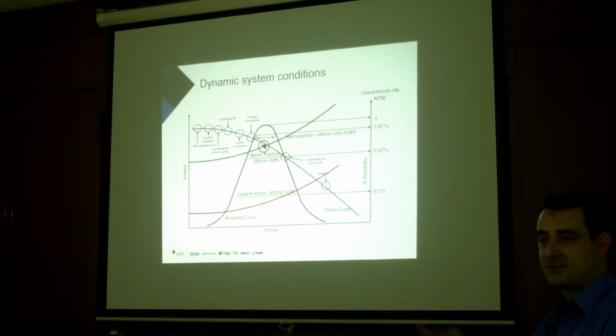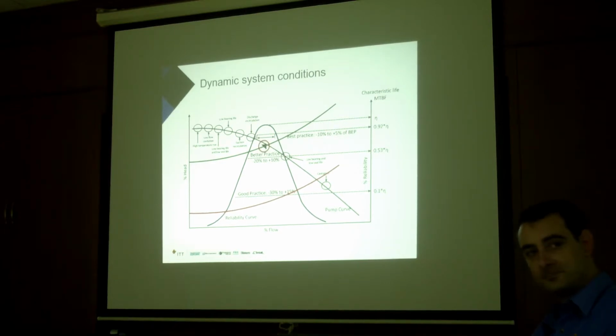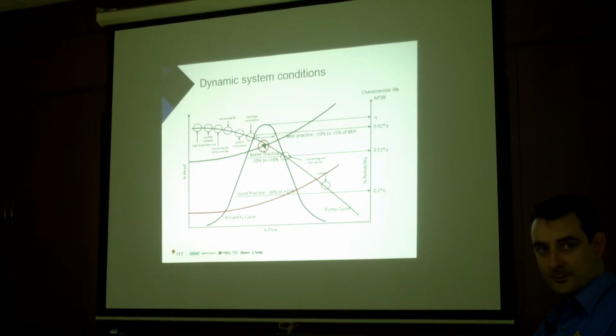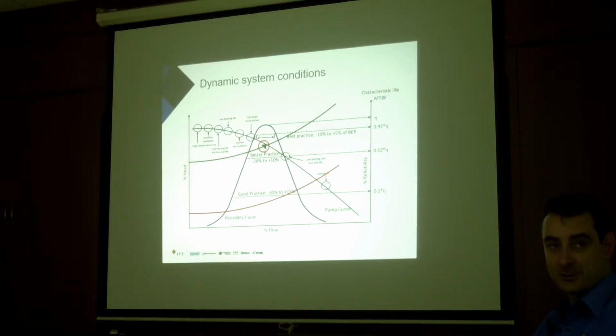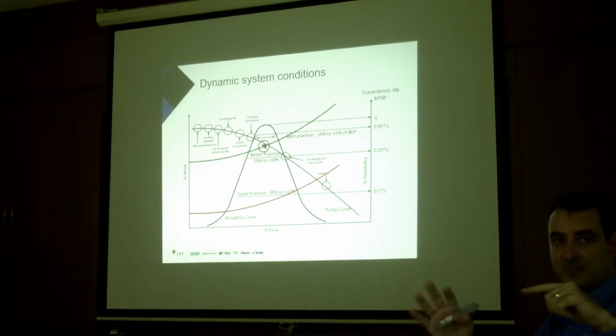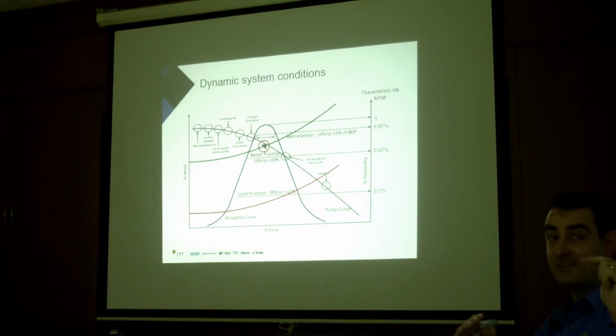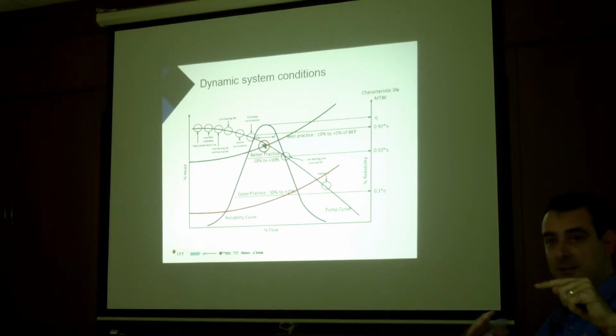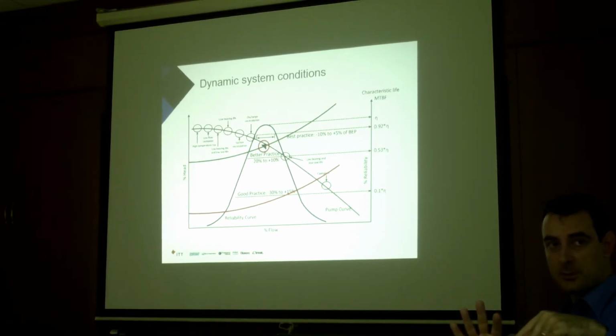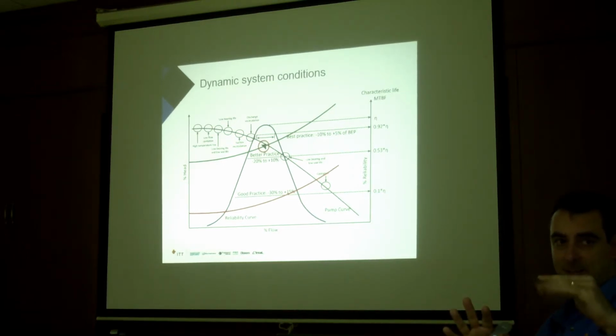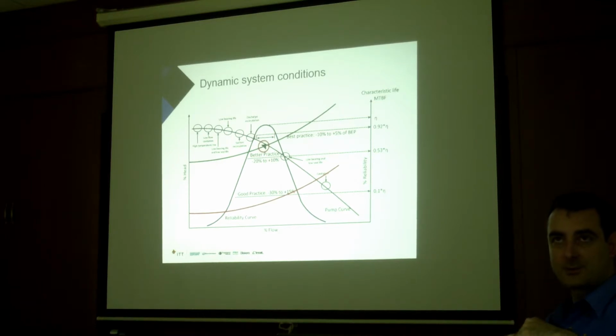Piping drawing, that's it. In case we have 4 trucks at the same time and 1 pump, usually 4 trucks, right? So what would Pump Smart do to control it, because the batch controllers do not open and stop at the same time? Yeah. So we usually run those on pressure control. So we look to maintain a constant pressure at the road gantry, at the batch controller. The only problem is if the pump is sized too small for that pressure with 4 trucks, then the pressure will drop. But as soon as one truck comes off, the pressure will go back up and then it will slow down again.